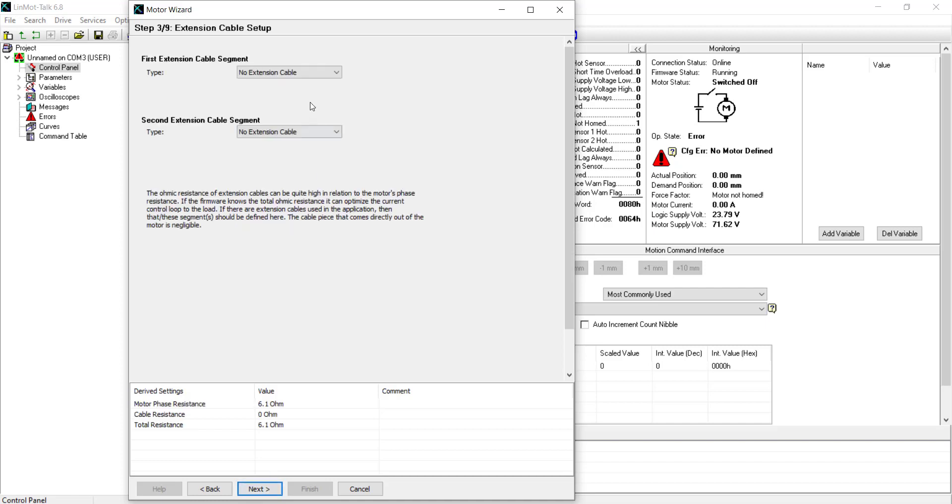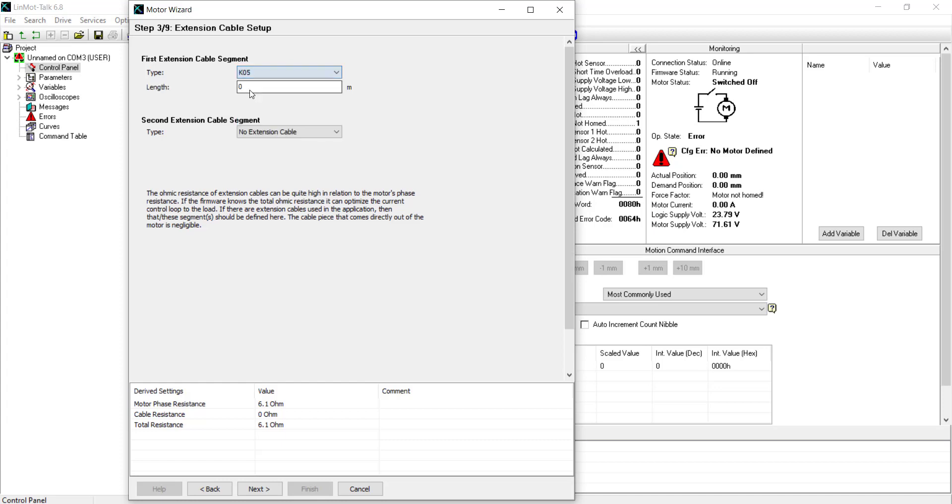In this step, the motor cable can be defined allowing the drive to compensate for the resistance of the cables. We are using the K05 half a meter. Cables are classified by cross-sectional area and length and can be identified via the bill of materials or the sticker on the cable. And this is completed so that LinMot Talk is able to configure the resistance of the cable.